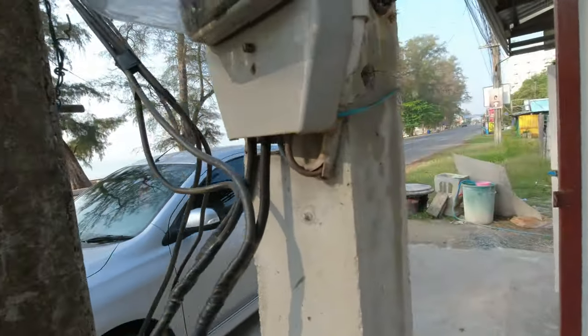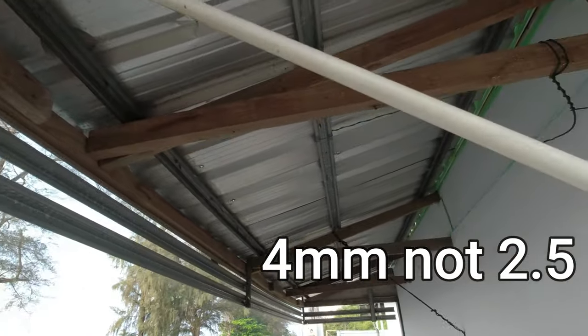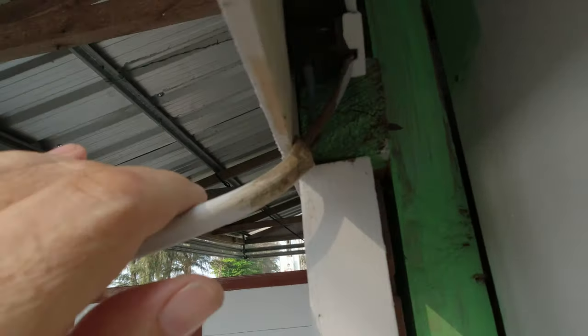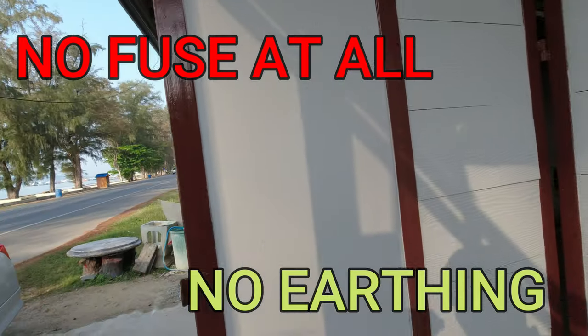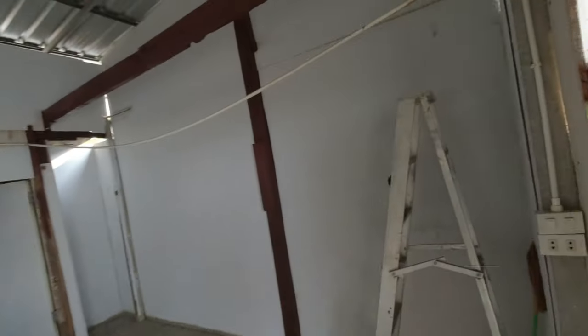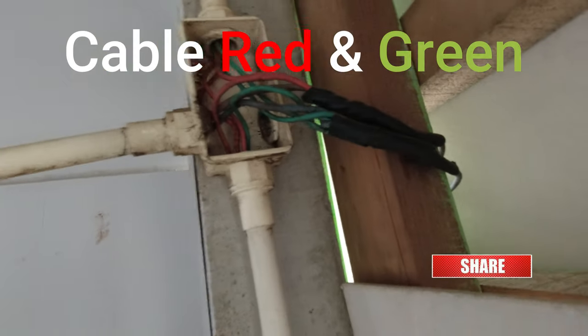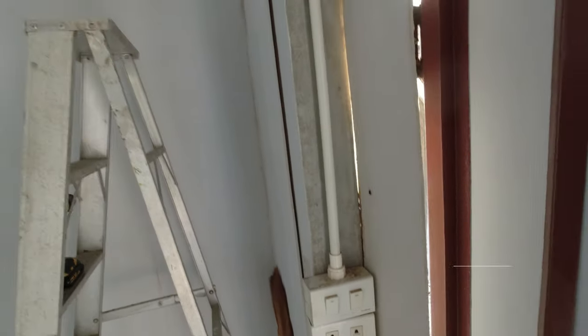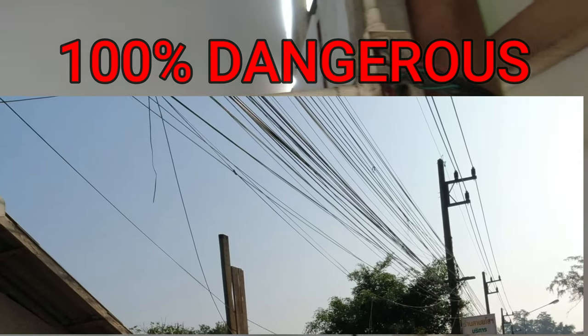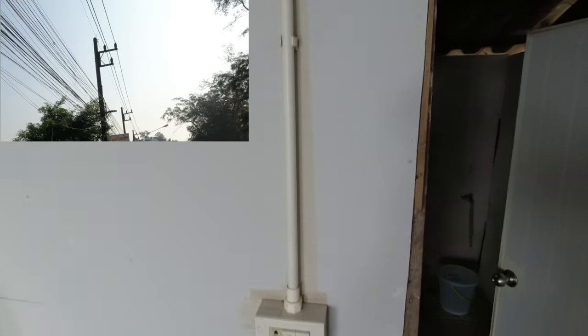That's the meter to the shop - 2.5 by the looks of it, and there's no fusing whatsoever. All of it is just an isolation switch. It comes into the building and everything's connected off there. So there's no isolation, there's no fuse board, there's absolutely nothing. The main isolation switch is for the fuse that protects the lines, so everything in here isn't fused at all, apart from the main fuse on the main lines, all the head lines.